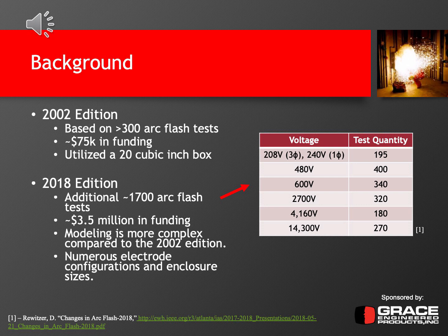And based on this data, they were able to determine an empirical equation that you could then, based on your own system voltage, apply a correction factor and then calculate the incident energy at your particular system voltage versus these 6 voltages, or 7 voltages, listed in this table.